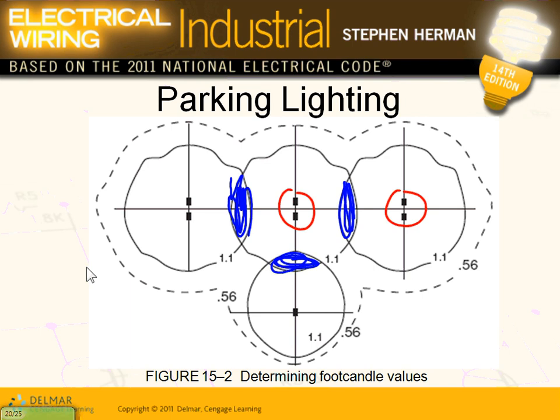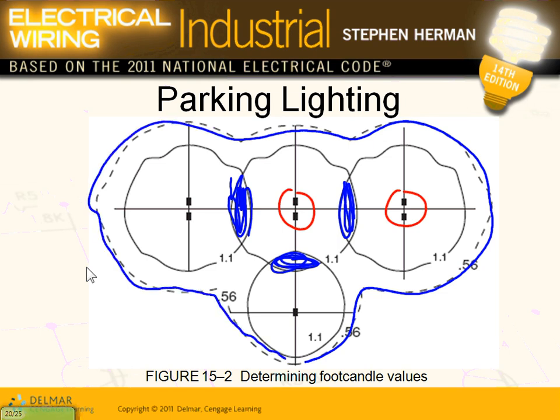You can have two heads, three heads, or four heads right on the pole, and Visual handles that well. You put your calculations on — you can make your calculations in any shape you want. Ours is usually rectangular. It will give you the max, min, average, and average-to-minimum. Max is the brightest, min is the darkest, and average-to-minimum is the difference between the brightest and the darkest.